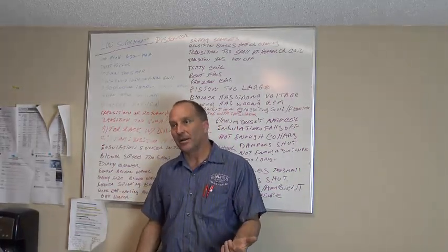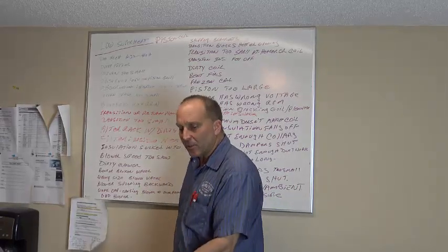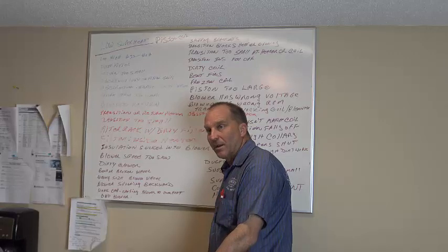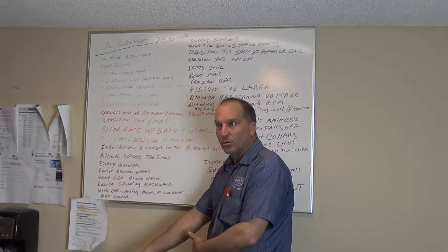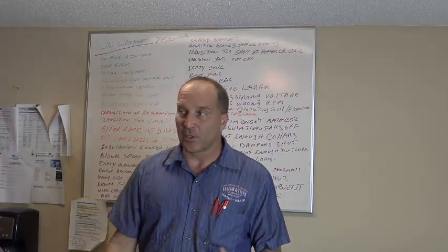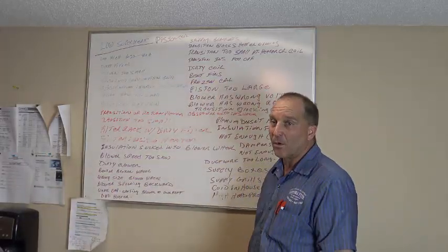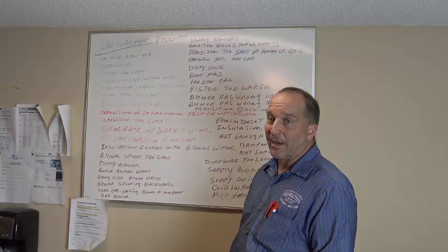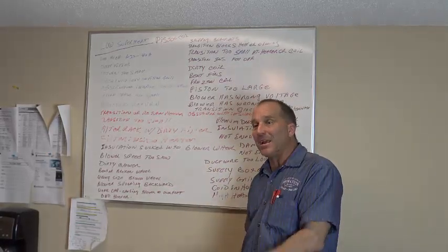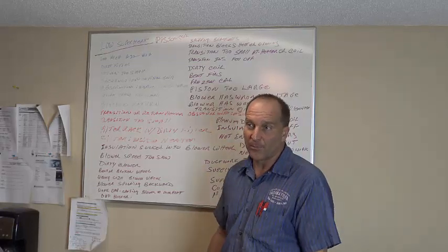So when that happens, you're restricting airflow through that system. You take a magnehelic gauge or an incline manometer, take your static pressure here, take it here, there's going to be a difference because the airflow is trying to get through and it's being restricted through that hole. It's too small. So always check your return plenums. Your return plenums a lot of times are too small. Your filter grill, I guarantee you, if you do height times width, I'm telling you, you'll probably find 98% of the time your filter grill is too small.